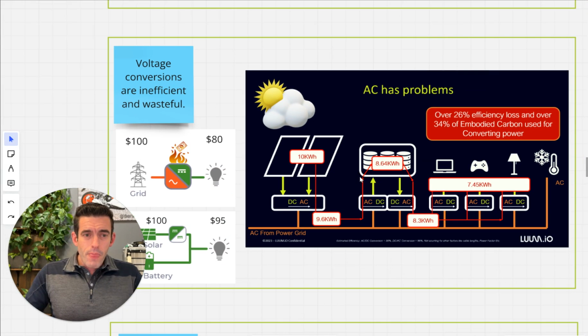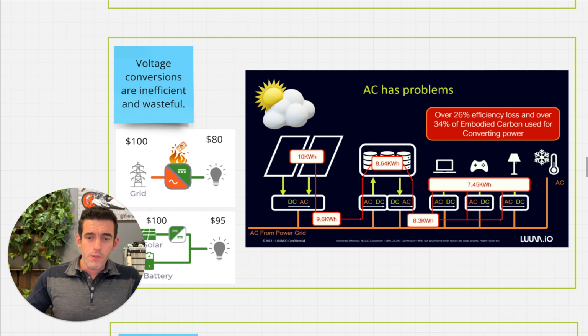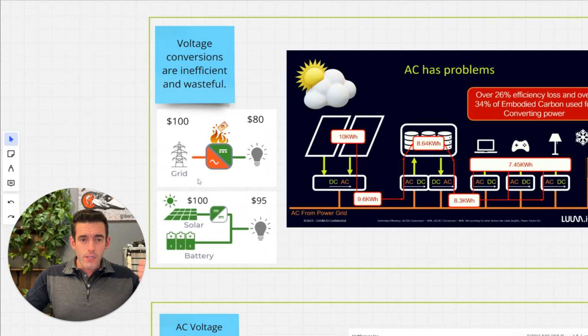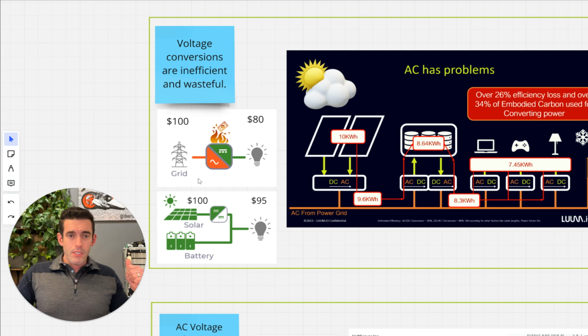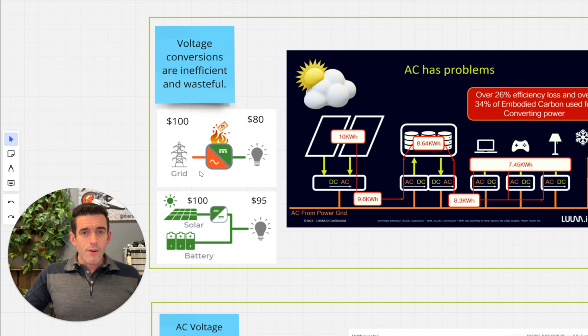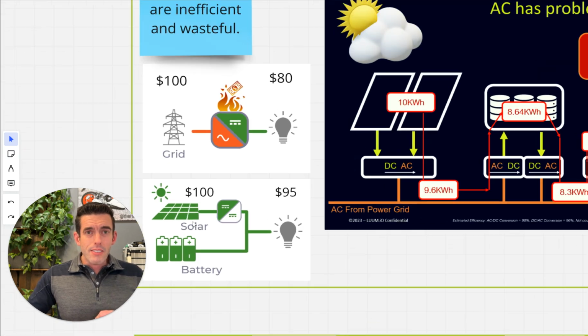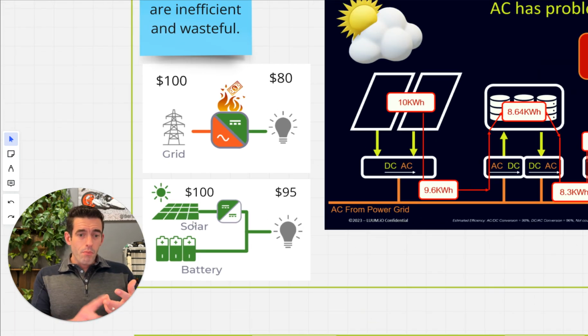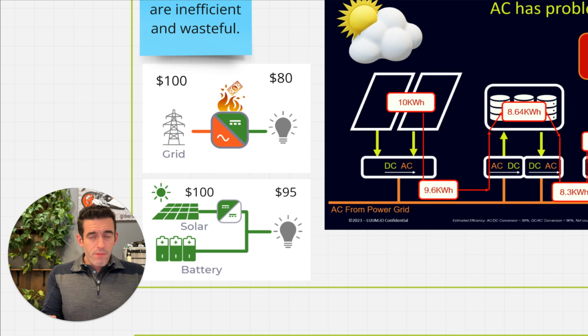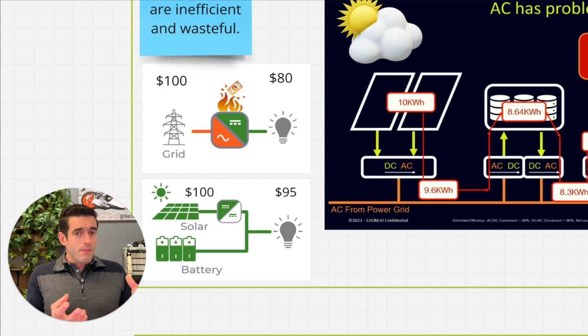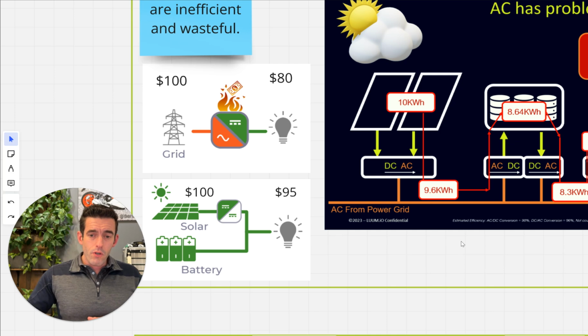Next challenge: voltage conversions are inefficient and wasteful. Think of it as $100 coming in at the side of my building. If I have solar and batteries in that building, by the time that energy gets to my light, I've only got $80 left. However, if I just take that as DC voltage energy - I have a battery, a PV array - I'd have $95 left when I got to my light, because I don't have conversion losses.